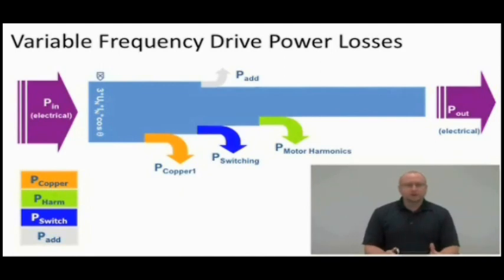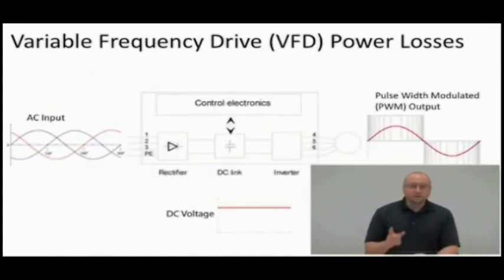If we look at the basic parts of an inverter, we have our AC power that's coming in. That goes into our input rectifier, where it gets changed to a DC voltage. And the control electronics of the inverter actually send out DC pulses to the motor. If you look at the output of the inverter up here above my head, you can see the little black boxes are the DC pulses. The red line is actually the average current level. So the black boxes are the voltage pulses that are coming out of the inverter.